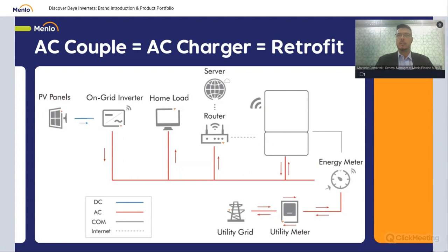So AC coupled equals AC charger equals retrofit. This is basically when you have a grid-tied system or an on-grid system, and you want to add storage solutions. Deye inverters support that. The on-grid system gets connected to the Deye inverter and basically becomes an AC coupled system. With that system, it can either charge or discharge the batteries. From the grid-tied inverter side, it will charge the batteries, but from the load side, it will be charged or discharged according to your needs. Next slide, please.